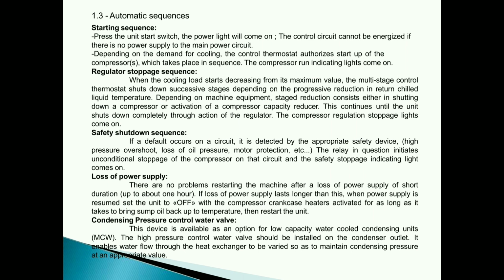There are no problems restarting the machine after a loss of power supply of short duration, up to about 1 hour. If loss of power supply lasts longer than this, when power supply is resumed, set the unit to off with the compressor crankcase heaters activated for as long as it takes to bring sump oil back up to temperature, then restart the unit. Condensing pressure controlled water valve.